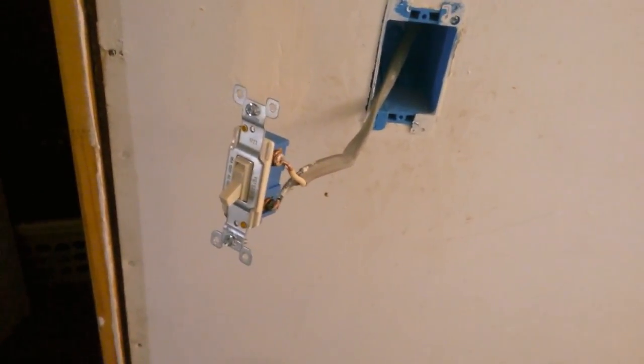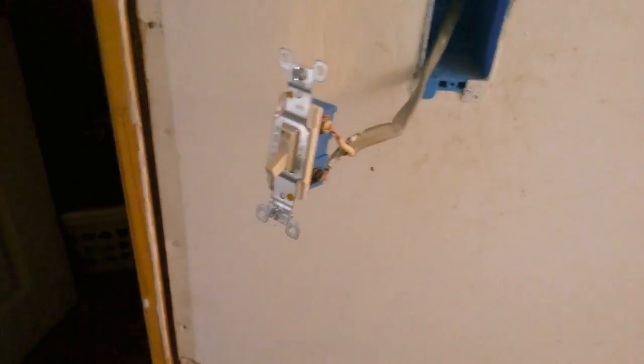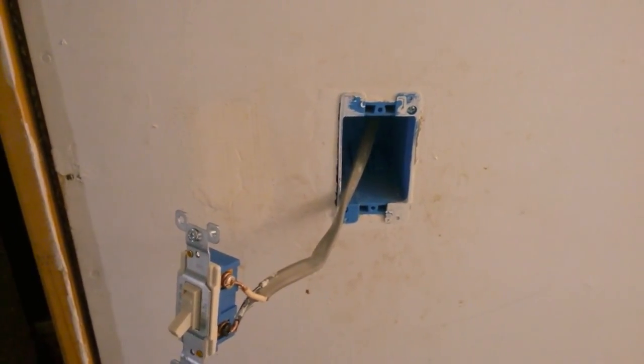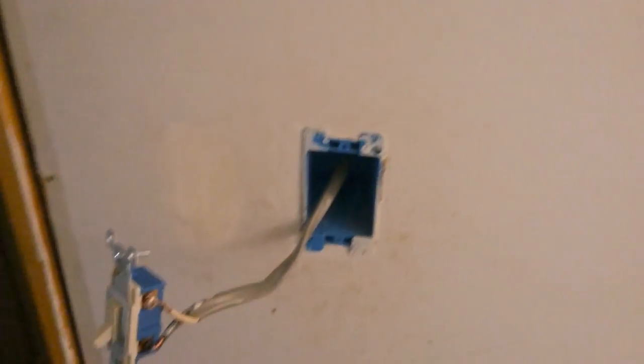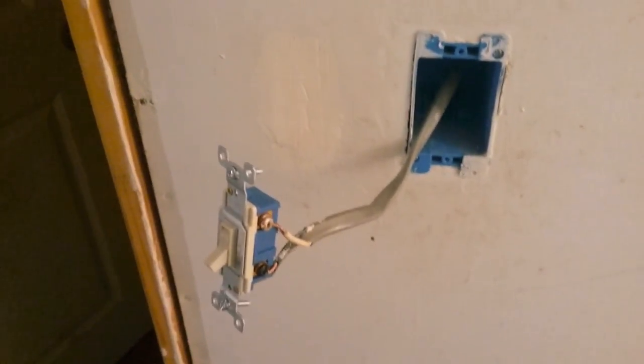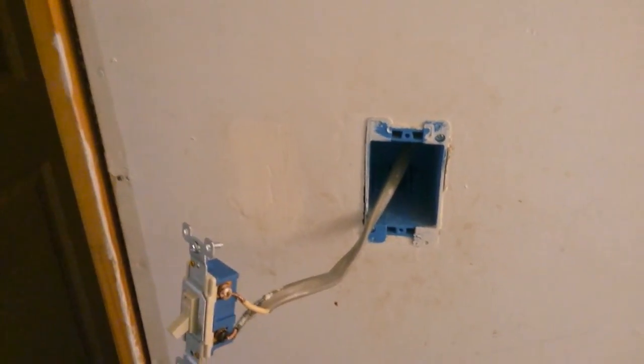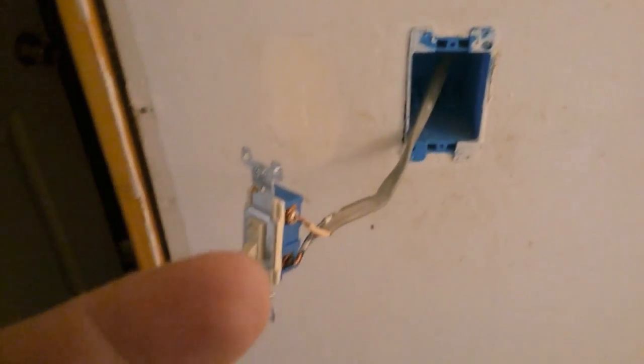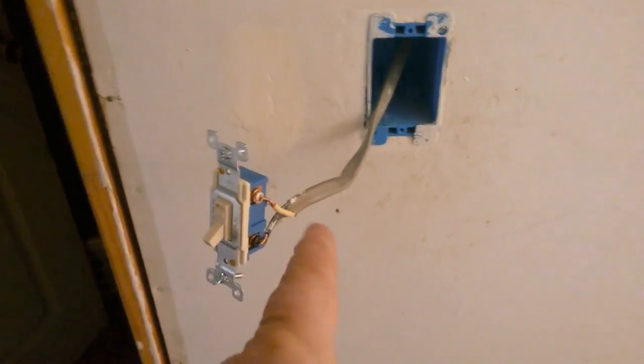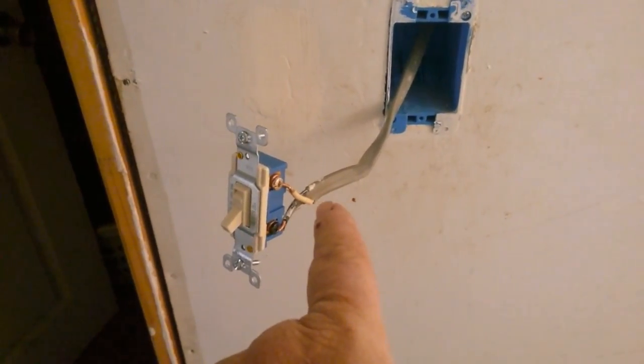Again, this home is a two, this part of the home has a two-wire non-grounded system. And that's what they did back in the old days, you know. So it's not what I would like, but I'm all for, when it comes to electrical, I want the three-wire grounded and every eight-foot ground rod in there, drove into the ground, all that good stuff. But sometimes in reality this is what you end up with. And you just got to be careful working on it. If your home does have a two-wire ground system and you're changing out ceiling fans or lights, always be careful. Because on most of them that I've run across, the white wire, which you would think would be a neutral not carrying current, even though the switch is off to that light, there's still current.